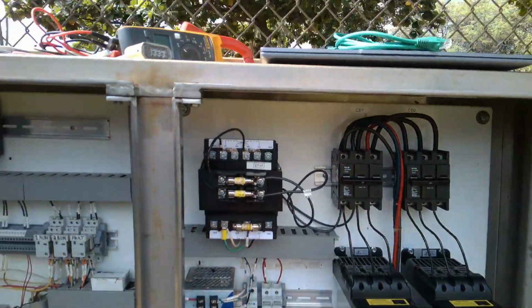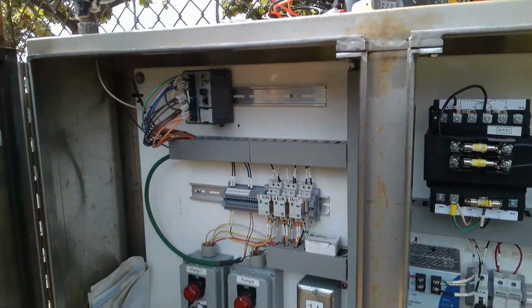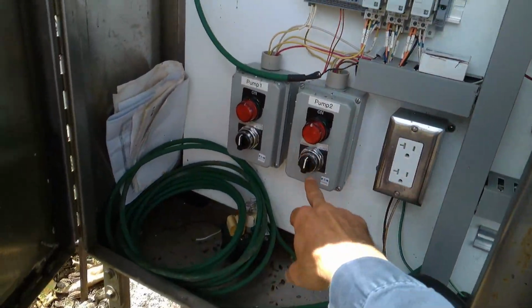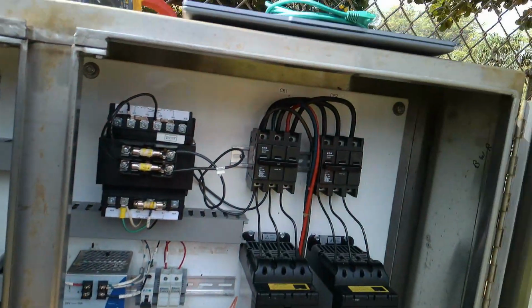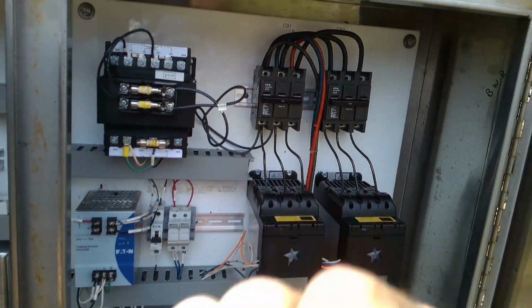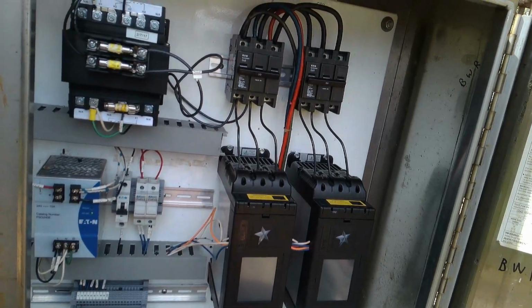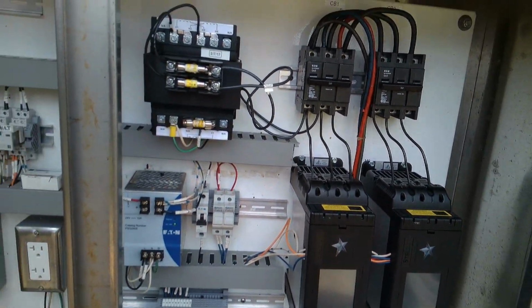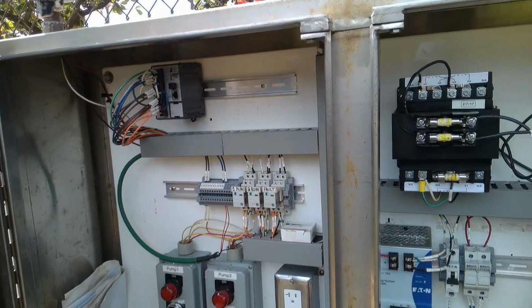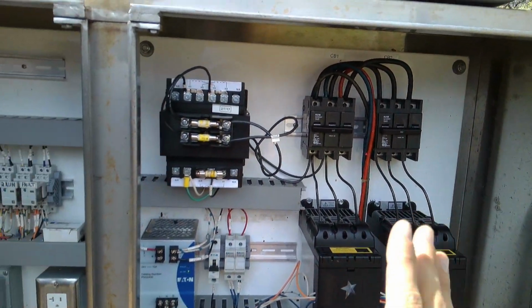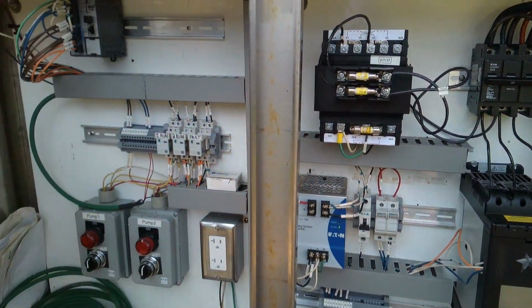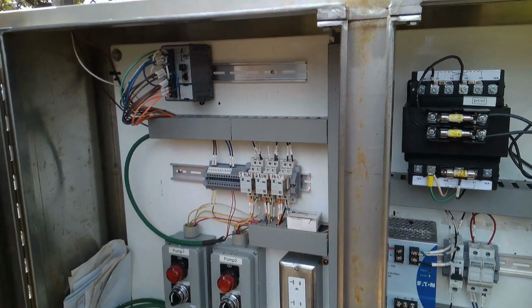Okay, so getting here. Upon arrival, pump selector switches are on off. Breakers for the soft starters are off. We've got two Automation Direct Stellar soft starters here. Everything's shut down. Did basic voltage checks just to make sure our supply voltage is good before we turn that on. Rule out any obvious major issues.